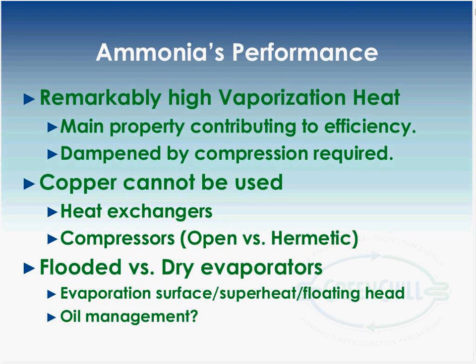And for the compressor, if you look at a standard rack with semi-hermetic compressors, the suction gas flows over the motor windings, which are copper, obviously, and cools the motor. So that's one difference: you would need to use an open compressor. It's kind of a catch-22, or maybe a little ironic, that using the open drive compressor actually gives you a little more efficiency in your system, because you don't have that extra motor heat in your suction gas, which ends up as heat the condenser has to reject. By having the open drive compressor, your motor is free to cool itself with the air around it, and that heat doesn't end up in the system. So it's a positive and a negative at the same time.